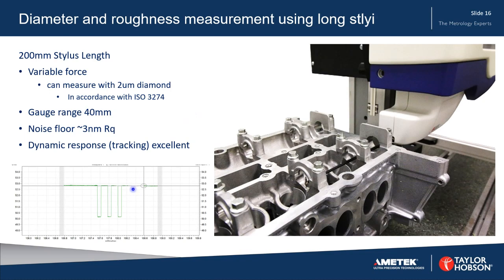On the base here, we can see that the dynamic response of such a stylus is excellent. If we repeat the measurements, this 3-line standard will show measurements overlaid on top of each other excellently without any deviations, and that's due very much to the ability of this system to control the stylus force of long styli.